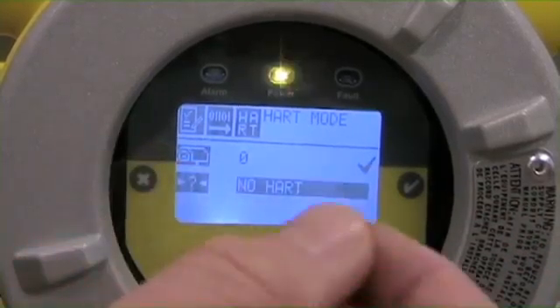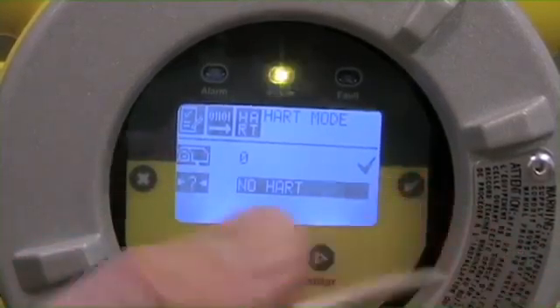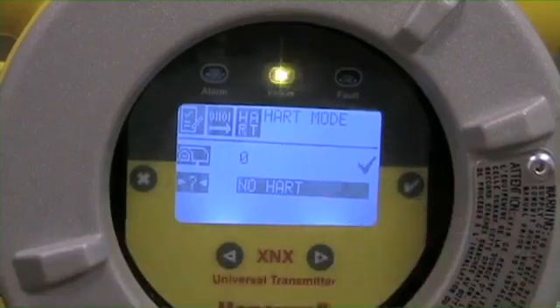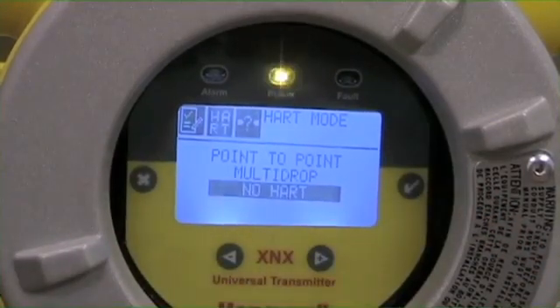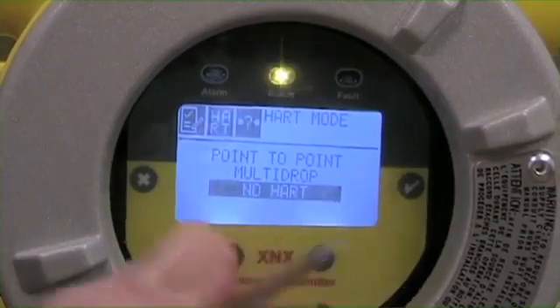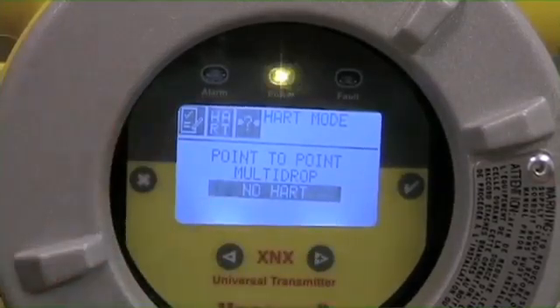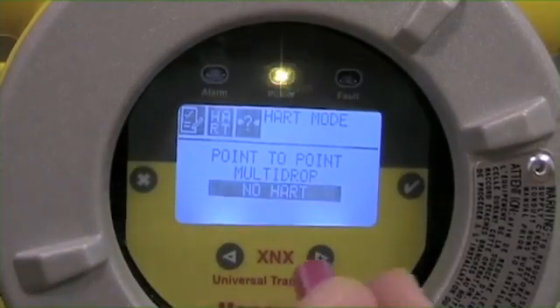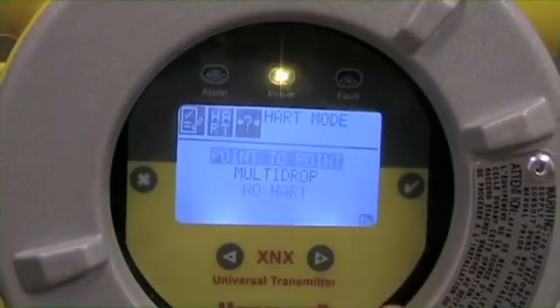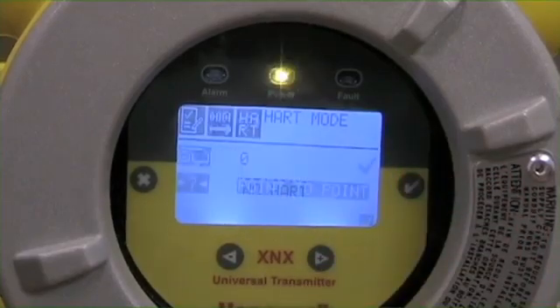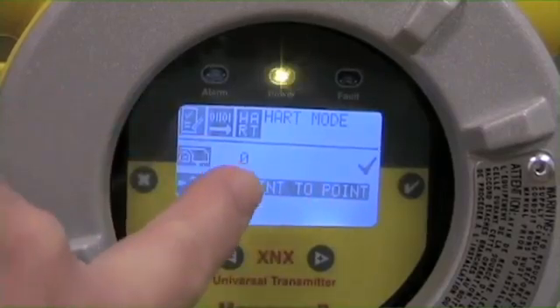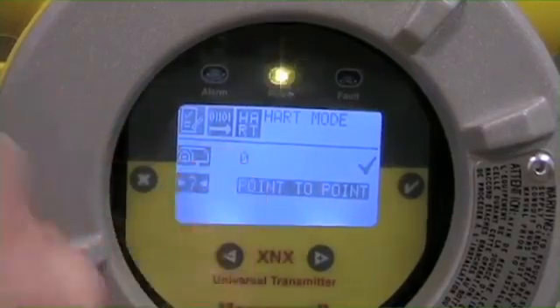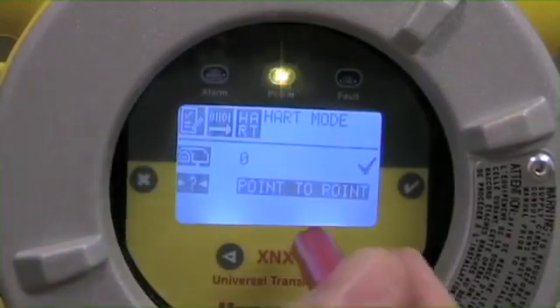In the next option, you've got the ability to set what kind of drop you're looking at. There's either no HART if you're not using the HART information, or if you've got a point-to-point strategy or a multi-drop strategy, you simply toggle over to that and then enter to accept. As with all these functions, once you've got that functionality selected, you always need to make sure that you accept it.